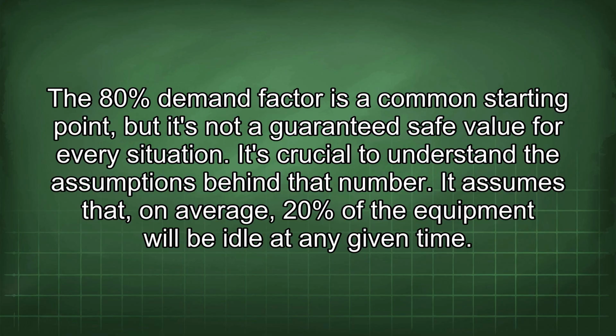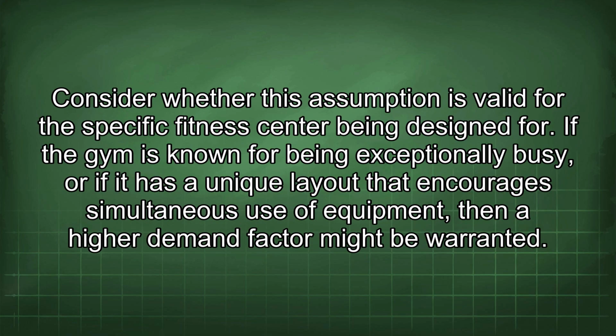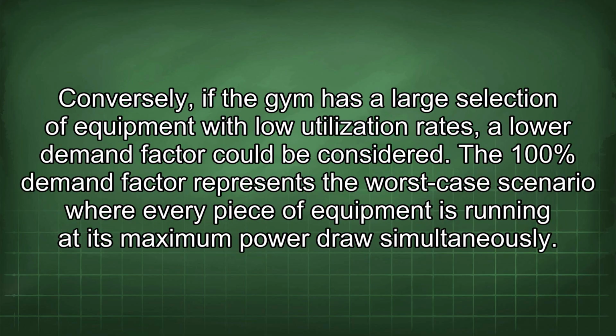It's crucial to understand the assumptions behind that number. It assumes that, on average, 20% of the equipment will be idle at any given time. Consider whether this assumption is valid for the specific fitness center being designed for. If the gym is known for being exceptionally busy, or if it has a unique layout that encourages simultaneous use of equipment, then a higher demand factor might be warranted. Conversely, if the gym has a large selection of equipment with low utilization rates, a low demand factor could be considered.